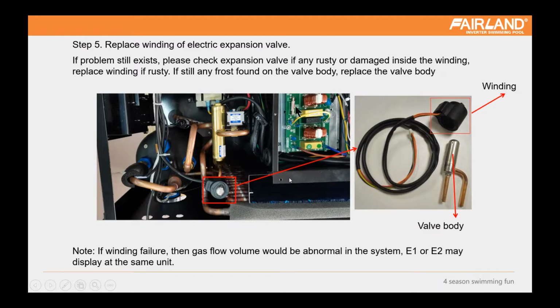And if not, finally, if you cannot find any reason for this high pressure, we will have to try to replace the valve body, because sometimes the valve body gets stuck inside. It's a very, very small possibility, but in theory it is possible. And if it is stuck, you can try to start the unit a few times, start and stop, to check if it can become normal. And another case we had before is one customer told us it had E1 and E2 at the same time on one unit, and that was the problem of this winding, the expansion valve problem.